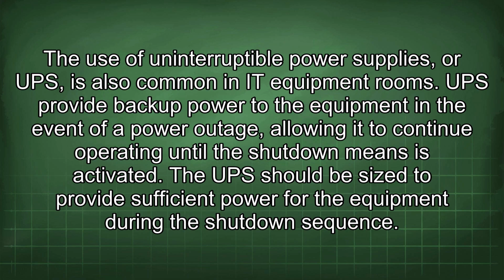The use of uninterruptible power supplies, or UPS, is also common in IT equipment rooms. UPS provide backup power to the equipment in the event of a power outage, allowing it to continue operating until the shutdown means is activated. The UPS should be sized to provide sufficient power for the equipment during the shutdown sequence.